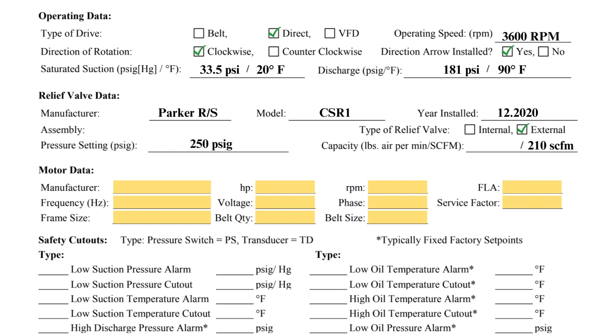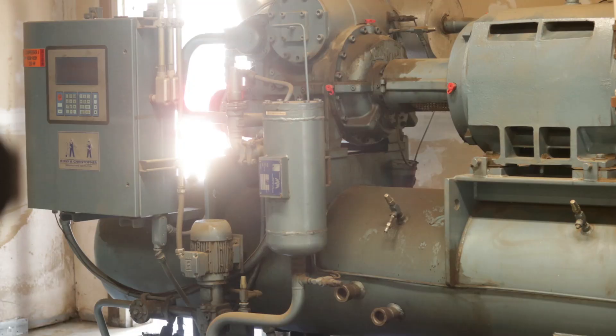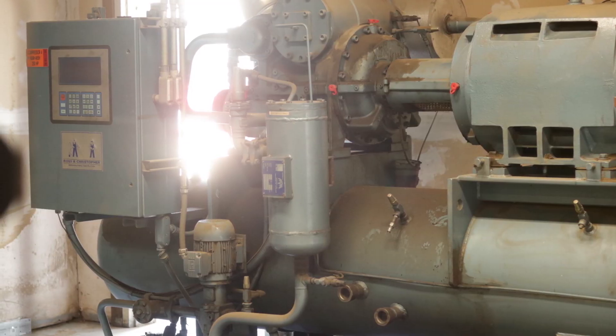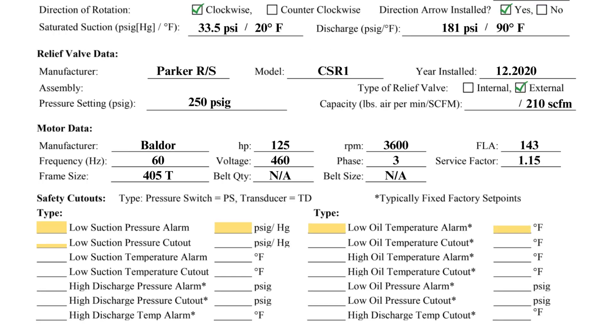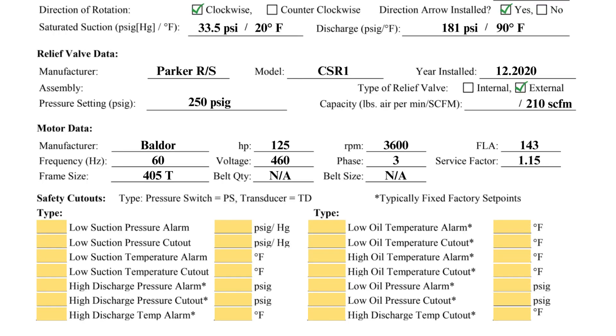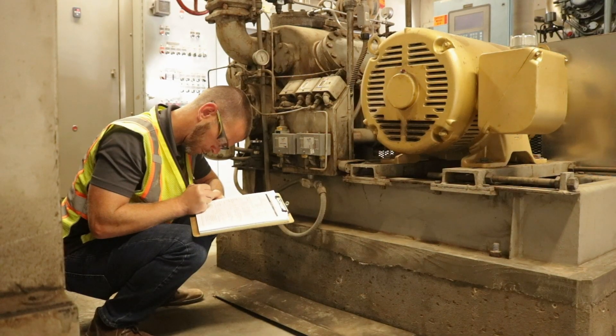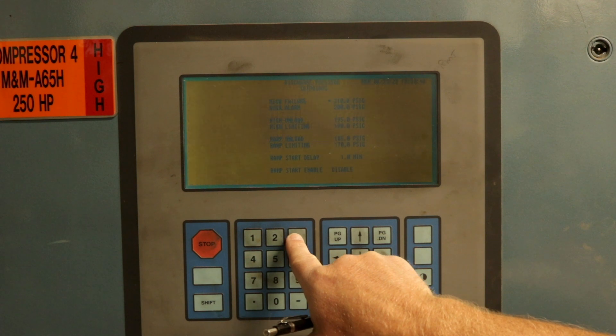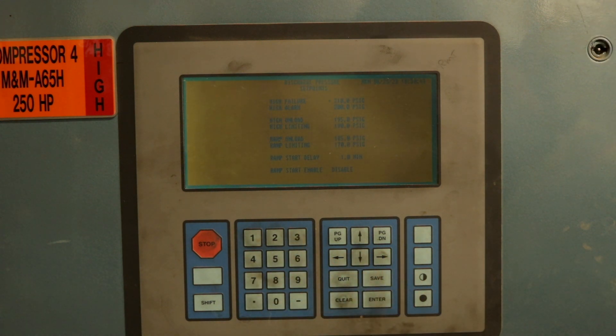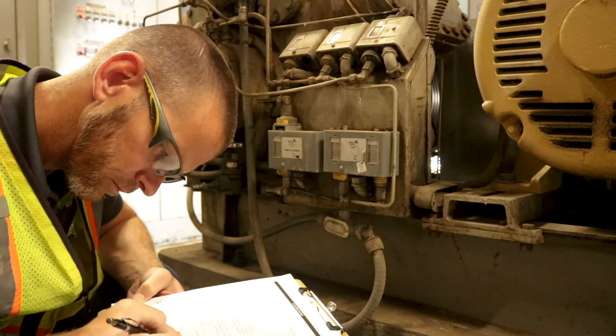The information required in the motor data section can be gathered from the motor's nameplate. Belt quantity and belt size are only applicable for belt-driven machines, so NA can be entered for direct drive compressors. The final information required on the first page pertains to the compressor's safety cutouts, which can be obtained from the electromechanical pressure switches on the reciprocating compressor or from the screw compressor microprocessor. At minimum, each compressor must have a low suction pressure, high discharge pressure, and low oil pressure cutout.